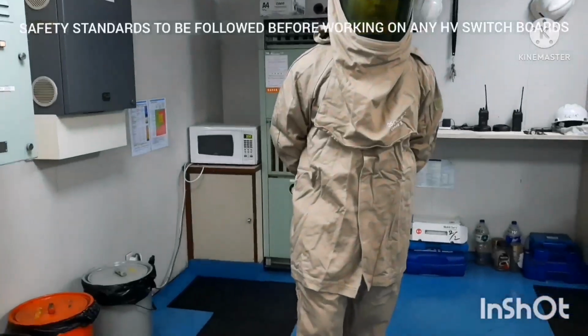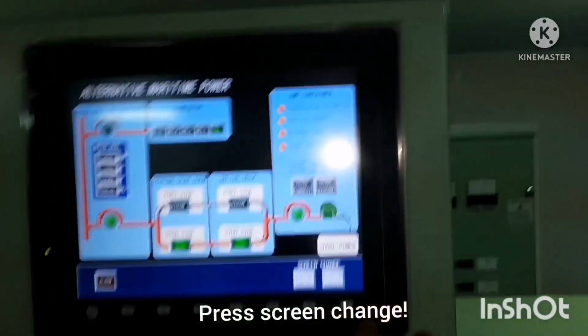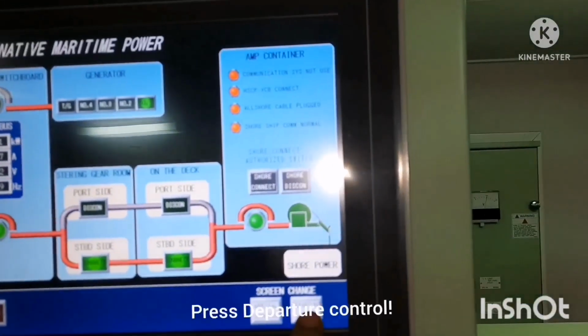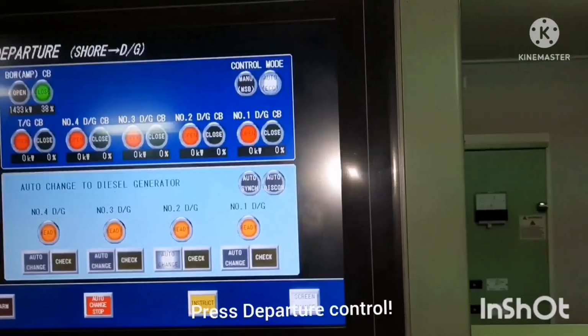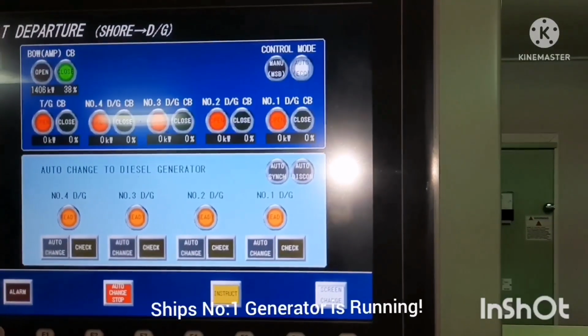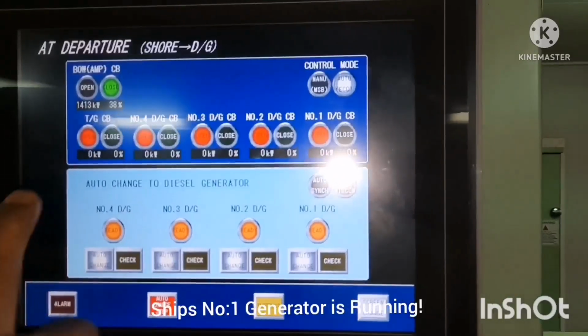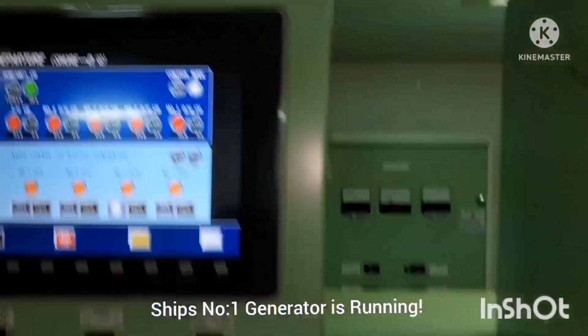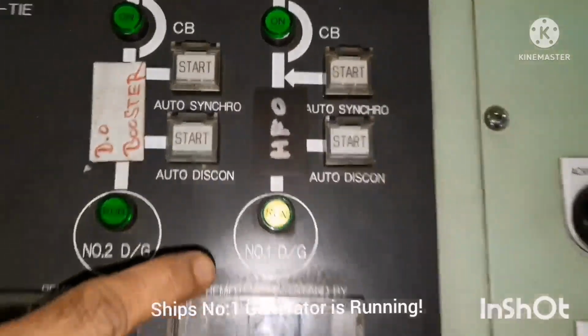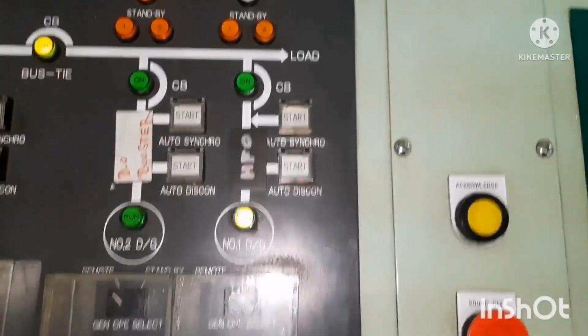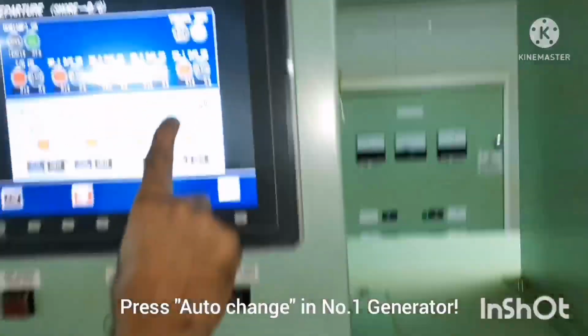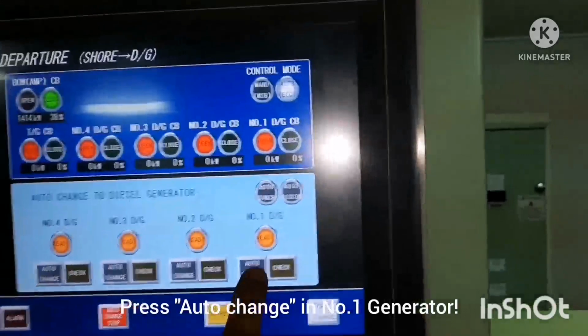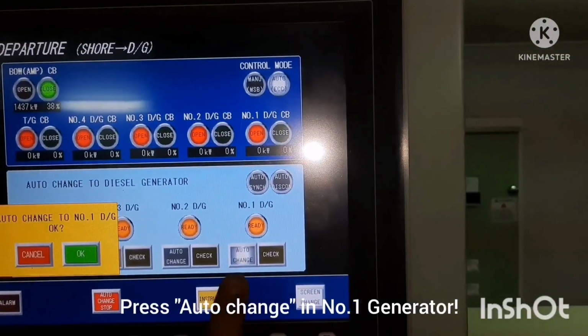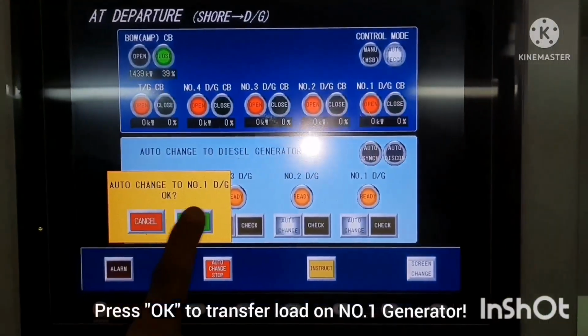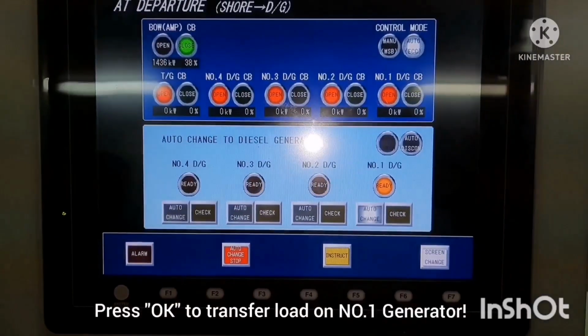Now we are going to remove power from shore and take the power from the generator. For that we need to press the departure control on the power panel. Now you can see the number one generator is running, the running light is indicated. Number one is running and not yet connected. Now we have to press auto change on number one generator. It will ask whether we need to change to number one generator. You have to press OK.